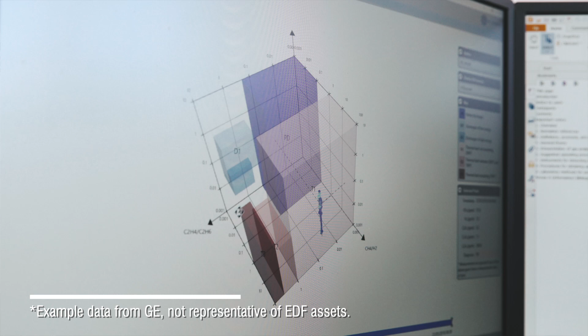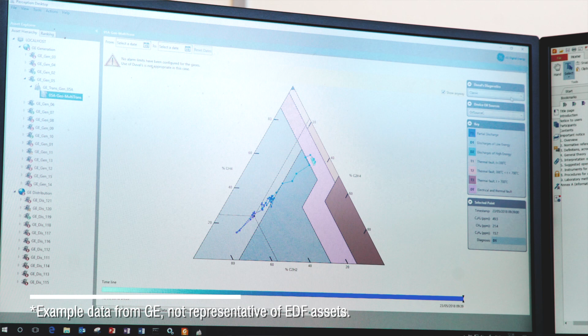That's one of the benefits. The station also have access to see the transformers from the safety of the office, see what's going on if we have any alarms come up. So if a transformer has a caution or an alarm comes up, then it'll email out to us, and it'll give you the latest. Well, our version will give you the latest. I think it's 2 lots of readings with all the gas details. So it gives you there, and then if you're not at your desk, you'll know exactly what gases are giving you the problem. Because even at a weekend, at least we know if there's something going on with the units.